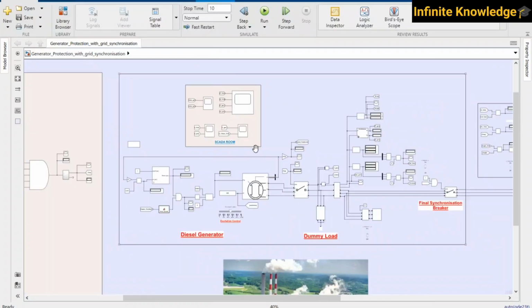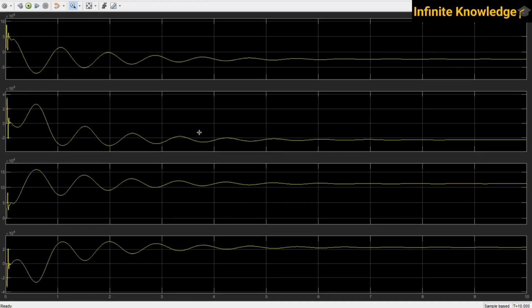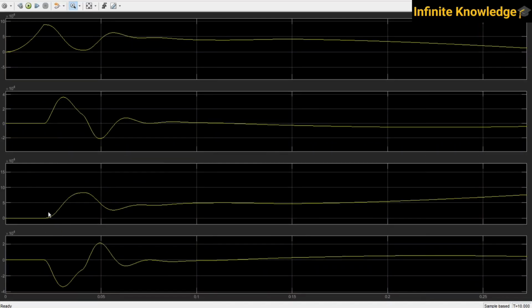And if you want to check power, you can check from here. This is the active power from the grid and the reactive power from the grid. Initially there is zero, and at this condition we have synchronized. As it synchronizes, the generator is feeding active power and taking reactive power. As it is feeding active power, the grid active power is reduced, and as it is taking reactive power, the grid reactive power is increased. So the power must be balanced in the system. If someone is feeding, someone is taking, and if someone is taking, another one is feeding, same to same.